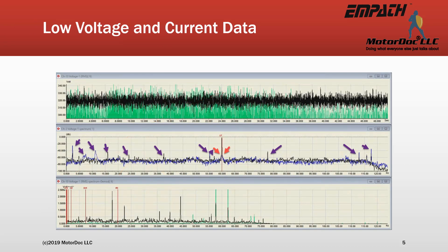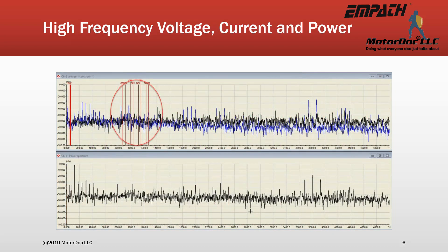The EMPATH system uses a number of types of spectra for analysis and includes voltage and current spectra for doubly fed inverter generators. This spectra is used for analyzing most bearing, gear, and some rotor issues. The high-frequency and power analysis spectra are used to look at gear mesh, rotor problems, and high-speed related issues closer to the generator.